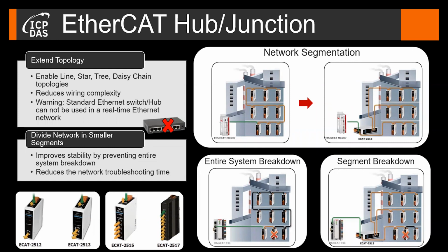ICP-DAS offers junction modules with 1, 2, 4, and 6 port branching. A junction has three purposes. It is used to extend an existing network by extending its topology. By using a junction, all topology variants can be implemented, like line, star, tree, daisy chain, etc. Its second usage is to divide the network into smaller segments to improve the network stability and prevent an entire system breakdown if one of the network systems fails.